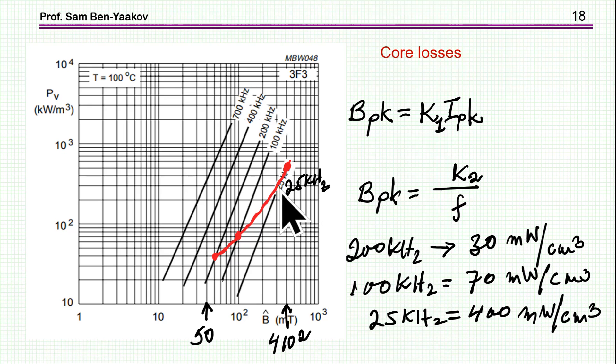And then if I go to 25 kilohertz, which is a lower frequency, which is four times lower, then the losses become very high. So clearly what is more important here is the fact that the B_peak is changing rather than the frequency.